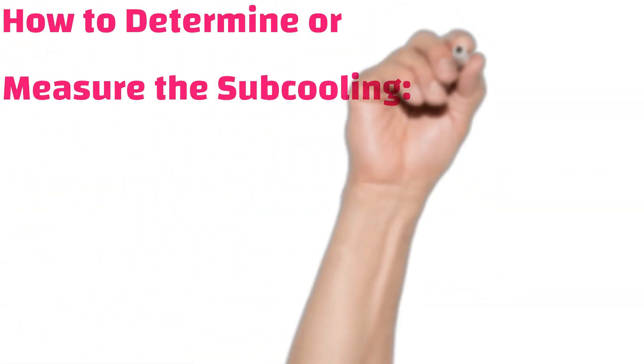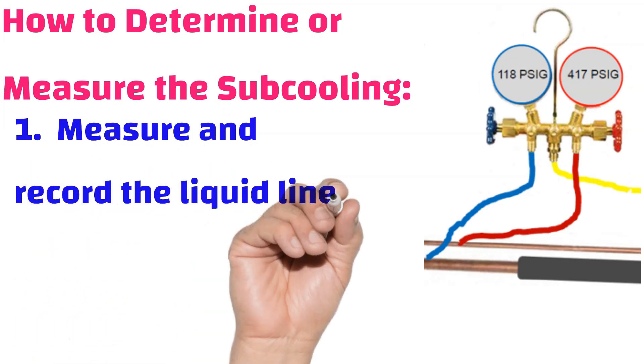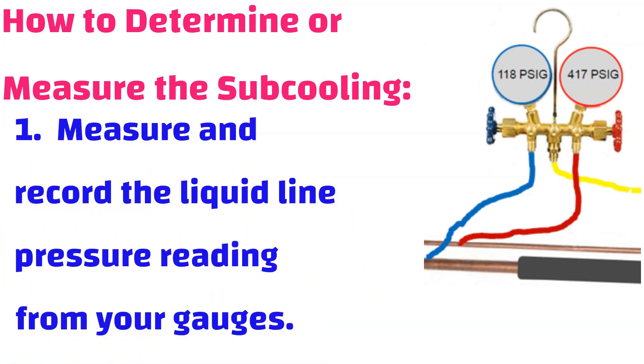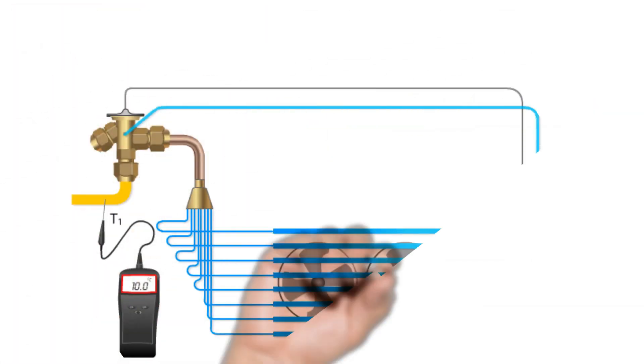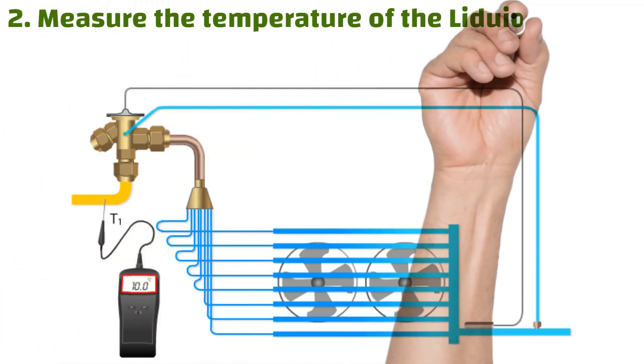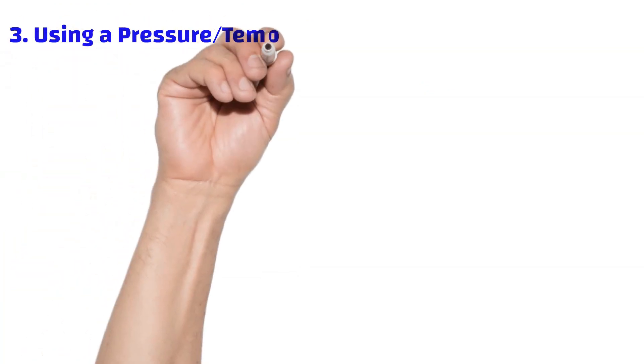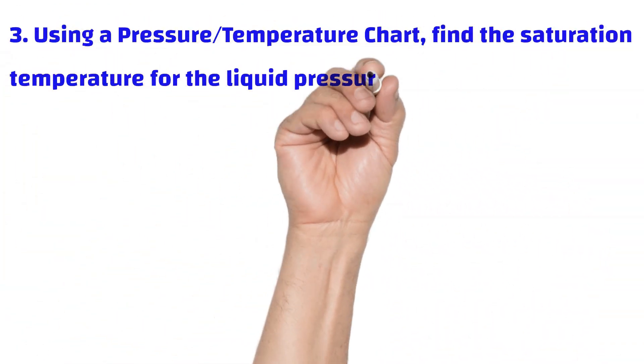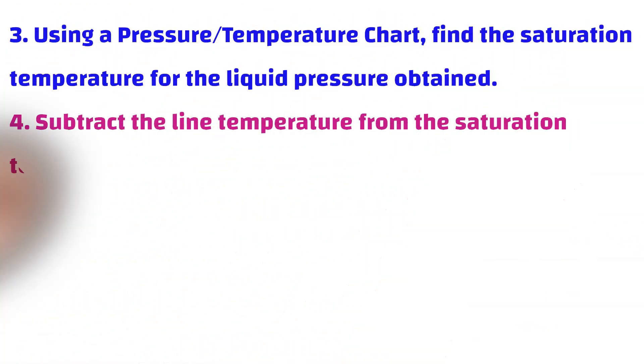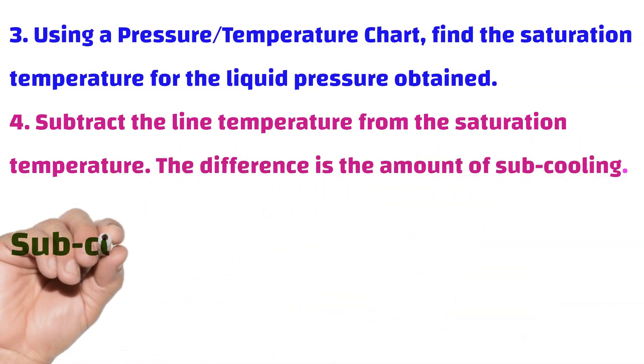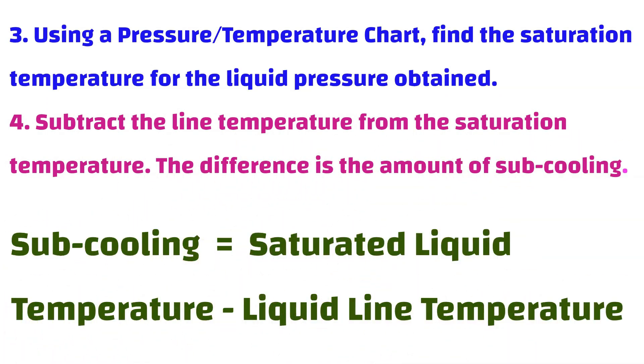How to measure sub-cooling: one, measure and record the liquid line pressure reading from your gauges; two, take the temperature of the liquid line after the condenser or before the expansion device; three, use a PT chart to find the saturation temperature for the liquid pressure obtained; four, subtract the liquid line temperature from the saturation temperature — the difference is the amount of sub-cooling. Sub-cooling equals saturated liquid temperature minus liquid line temperature.